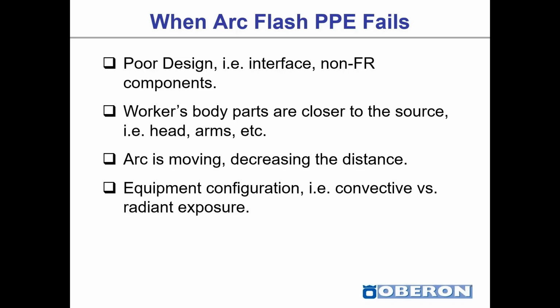However, we often work with our hands and arms extended towards the arc, and as you get closer to the arc flash, the incident energy would be exponentially higher. You know, distance is your friend. If you get farther away, it's the inverse square relationship, so the incident energy drops as you get farther away from the source of the arc flash. If the arc is moving, it can decrease the distance. The arc could be closer to the worker, and you're going to see some localized spots where we're going to have more heat than others. And equipment configuration, meaning convective versus radiant exposure.